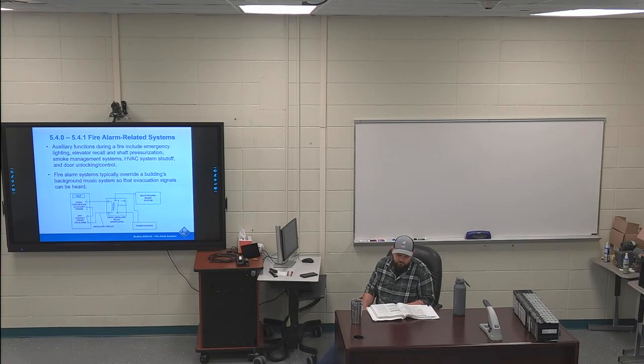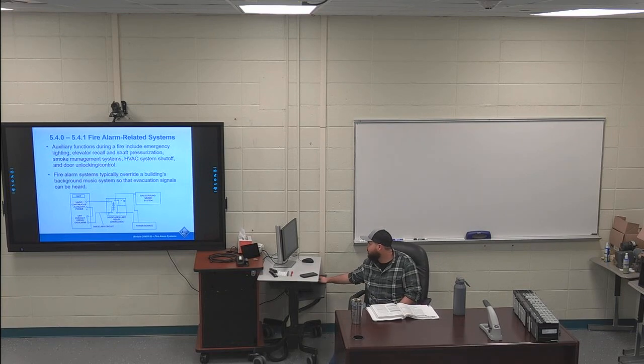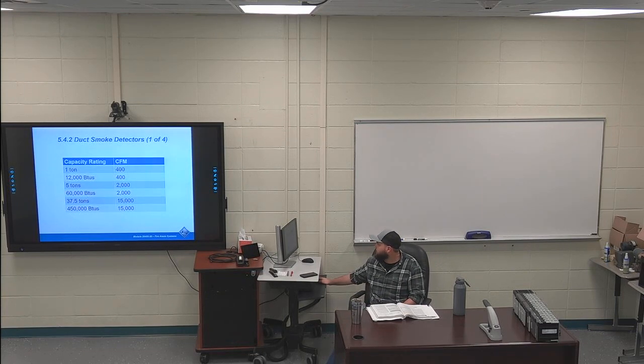Going on to page 57, 542, you've got duct smoke detectors. So this is ductwork that's in the ceiling and stuff like that. On page 57, the third sentence is highlighted. Duct smoke detectors are normally listed for a slightly higher velocity of air movement and are tested under UL's 268A standard. The next sentence is also highlighted.